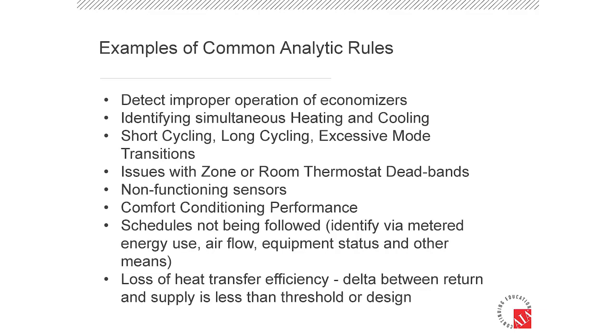Improper operation of economizers is one of the biggest issues, right? Simultaneous heating and cooling, right? Anybody ever detected simultaneous heating and cooling in a commissioning project? Yeah, okay. But it never happens, right? How could that possibly happen? A heating valve won't close after the winter, so it's still passing hot water through, and now it's in cooling mode. That's simultaneous. Everybody thinks, well no, it means somebody turned on both at once. Not that simple. But that's a pattern that can be detected, right?